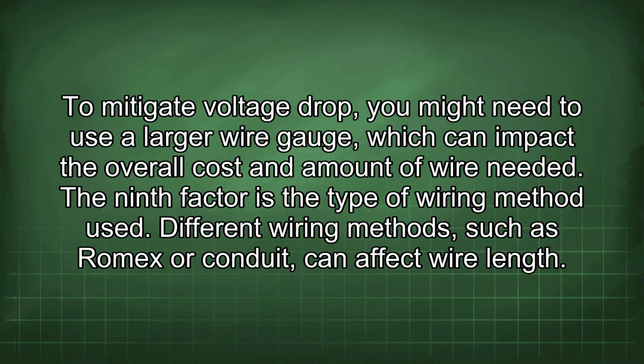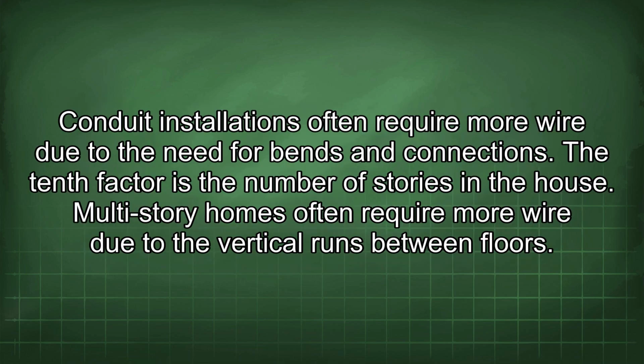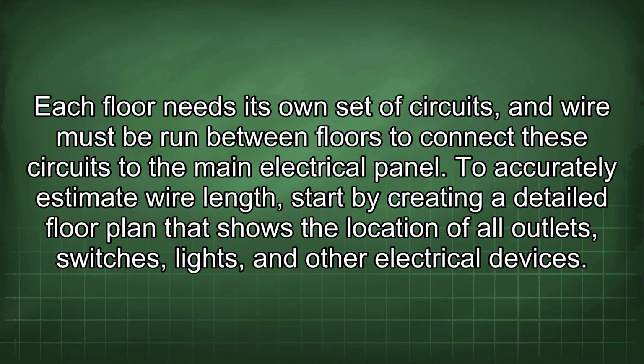Different wiring methods, such as Romex or conduit, can affect wire length. Conduit installations often require more wire due to the need for bends and connections. The 10th factor is the number of stories in the house. Multi-story homes often require more wire due to the vertical runs between floors.